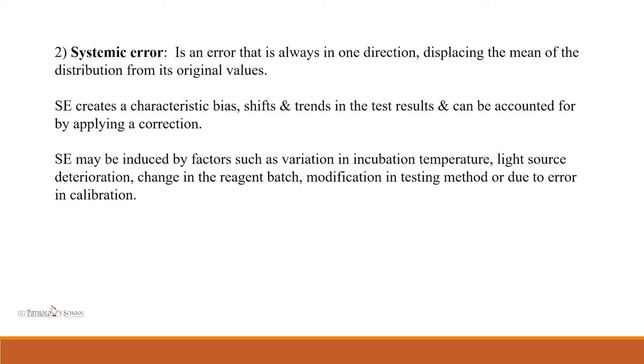Systematic error is an error that is always in one direction, displacing the mean of the distribution from its original value. Systematic error creates a characteristic bias — shifts and trends in test results — and can be accounted for by applying a correction. Systematic error may be induced by factors such as variation in incubation temperature, light source deterioration, change in reagent batch, modification in testing method, or error in calibration.